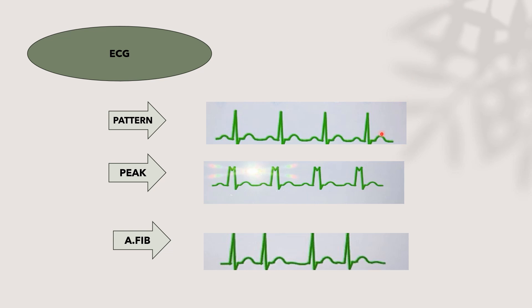The second type is the peak type, similar to the pattern type but used when there is a wide QRS complex, such as in bundle branch block. The third type is atrial fibrillation mode, where the machine analyzes the QRS complex in the same manner as peak mode, but the balloon automatically deflates whenever the R wave is sensed.